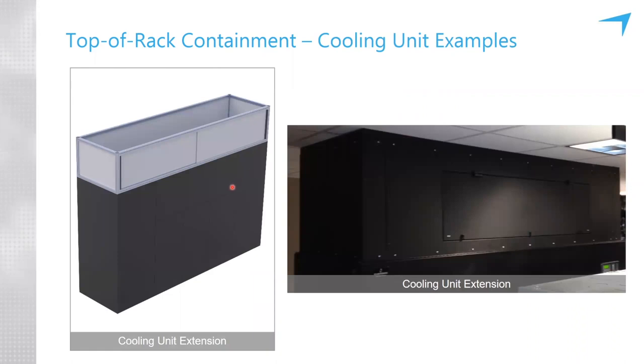Also, when doing hot aisle containment, in addition to the chimneys that are directing the hot air from the hot aisle, the exhaust of the IT equipment, into the ceiling plenum, you need to duct the cooling units to the ceiling plenum so that they're pulling the air out of the drop ceiling down into the cooling unit. There are a number of ways to achieve that, either bent sheet metal or an extrusion frame that sits on top of the cooling units. And of course, these need to have access panels so that you can access the filters and other components at the top of the cooling units.